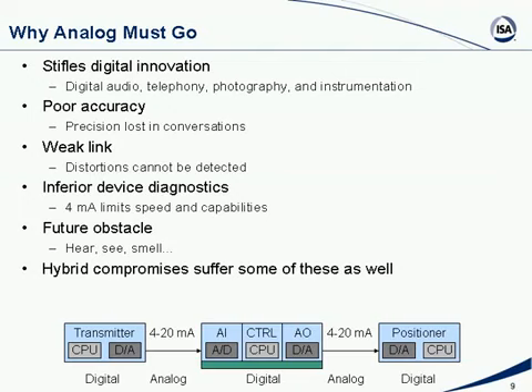Fieldbus provides more power to the devices. They are no longer limited by 4 milliamps. They can run on 12 milliamps or more, in fact. So that also allows them to have more powerful diagnostics, since microprocessors can run faster, and you can even create new devices that were not possible before. Communicating using Fieldbus allows us to get more information from the devices, so we can do device management from the central control room. And we will look at a later part of the presentation how intelligent device management allows us to reduce the cost of maintenance and operation.